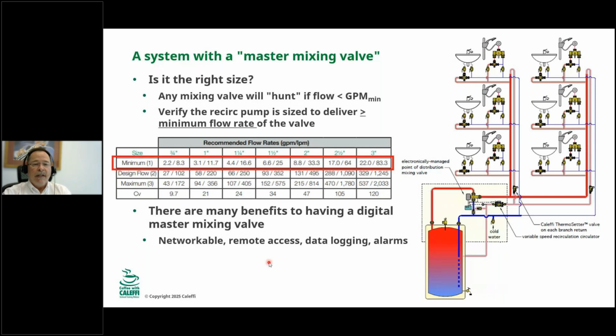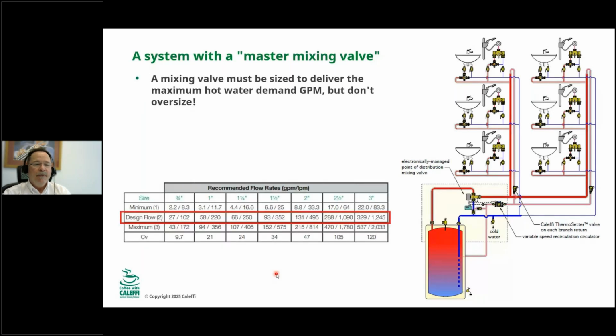Also, in addition to a minimum, valves have maximums or design flow. So no matter what brand you buy, look at their data and make sure that you use the valve that's the right size for the design flow or the CV that's recommended. Again, if you pick a valve too small, it's not going to be able to handle your heaviest times of demand. And if it's too big, then it will hunt a lot. So pay very close attention to the flow rates, the minimum, the design flow, and the maximum flow rates when you're sizing your valve.